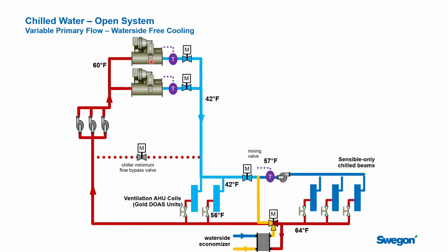In this example, though, we're going to look at a water-cooled chiller plant. So again, we're still showing you a variable primary flow system. We're not showing you the cooling tower loop, but these chillers would have condenser water coming from a cooling tower plant outside of the building. The chillers, of course, are rejecting their heat to the cooling towers. A cooling tower temperature would be optimized to improve the efficiency of the chillers. Design days are usually 85, 95 temperature, but in shoulder weather, lowering this cooling tower plant down closer to 65 degrees, if the outdoor air wet bulb will let you do that, will greatly improve the efficiency of the chiller plant, and so it's something to consider. And so we're starting to get pretty close to making water that we could use out here at the beams.